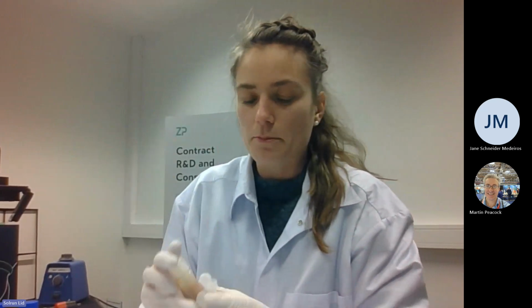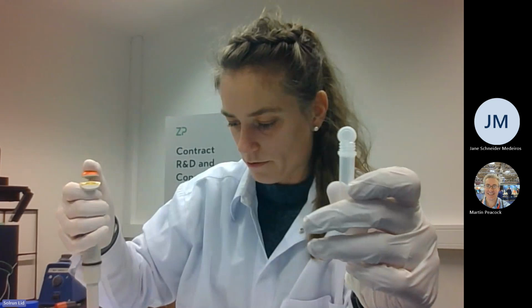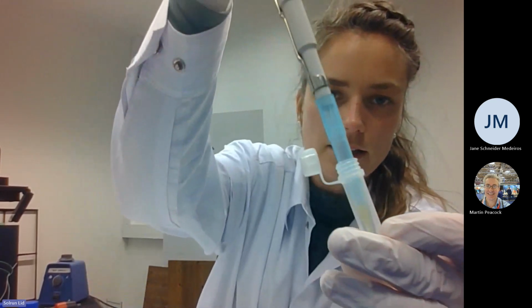And yeah, so the next sample we will test is the ginger sample. So we have a ginger shot sample here, so I'll just shake it a bit again just to make sure that we have a homogeneous sample. This is also not too high of a concentration of gingerol, so we'll prepare a 1:10 ratio for this one as well. So what I will do is I will add 100 microliter of the ginger sample into the vial, just like that.